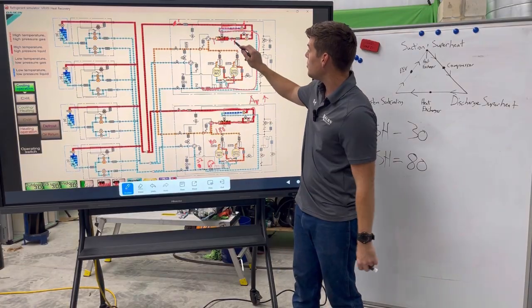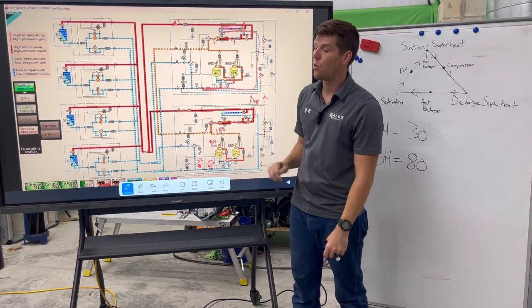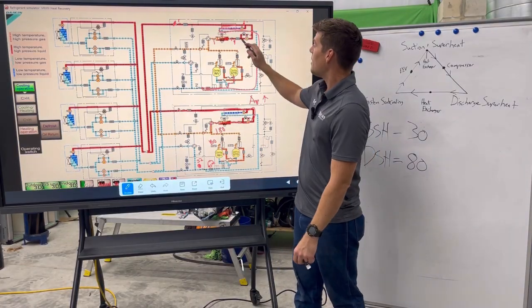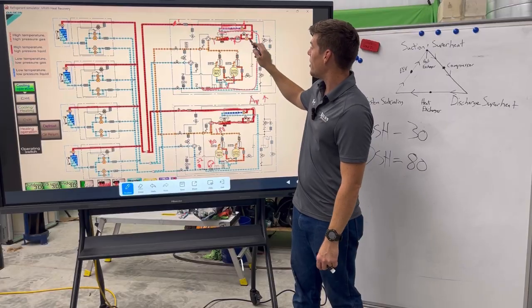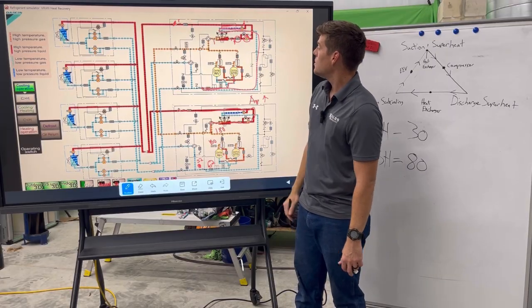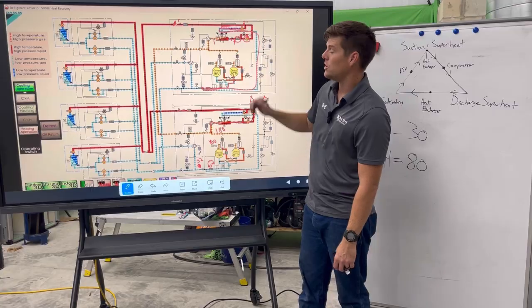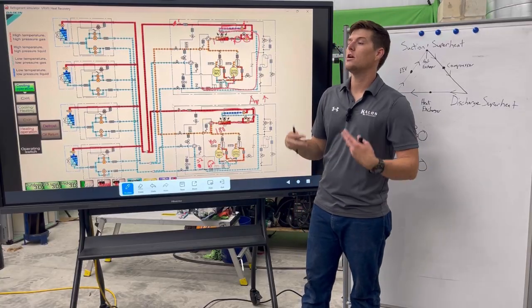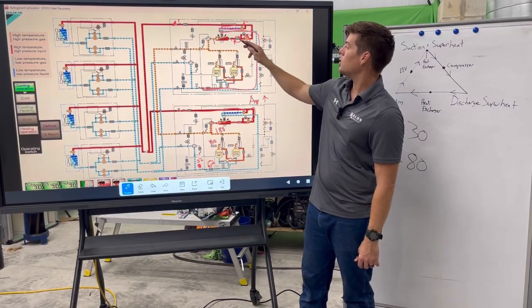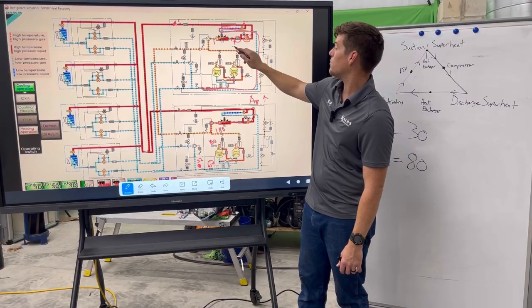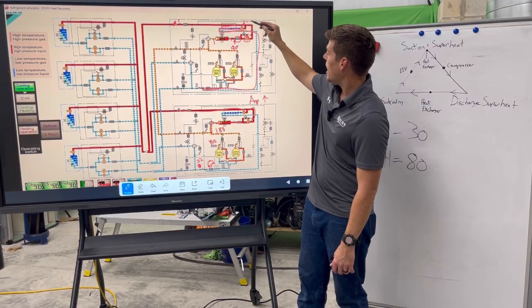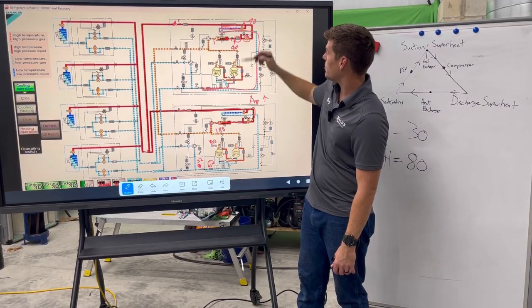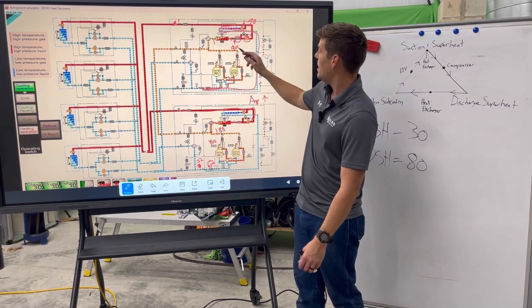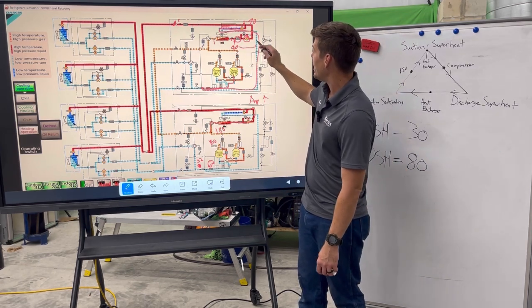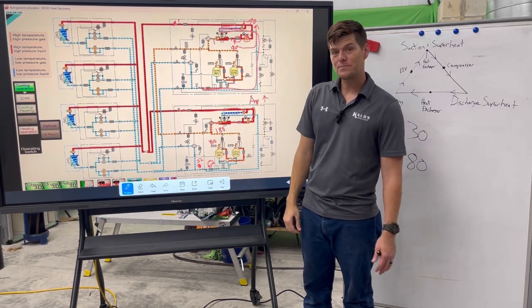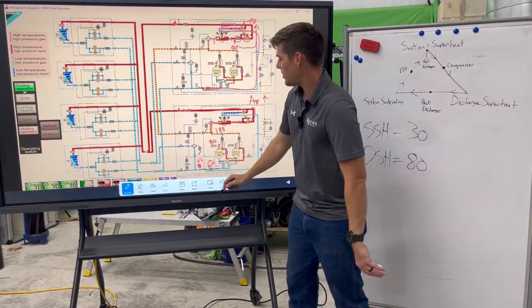This sensor is also used for measuring superheat across this coil in the heating mode. Because again, I'm catching it before this refrigerant strainer and before this expansion valve. So if there's issues with this expansion valve or materials clogged up in that actual strainer, I'm not going to get a good temperature. I might have a temperature drop. Maybe it goes from 90 degrees from here and on this other side it's 70 degrees. Well, that's a big issue. There should not be a 20-degree drop between here and here in such a small area. That's a red flag. But that's not what we're here to talk about.